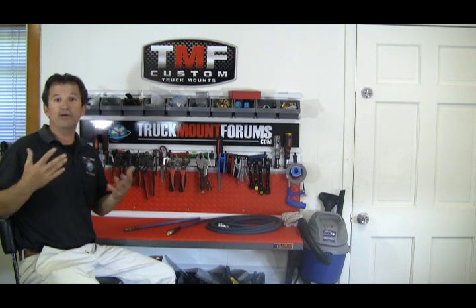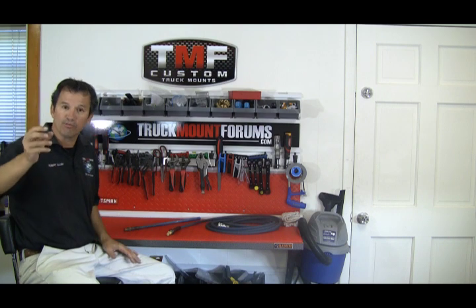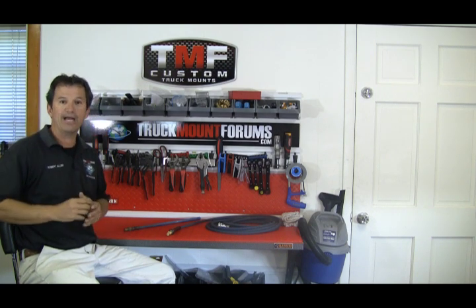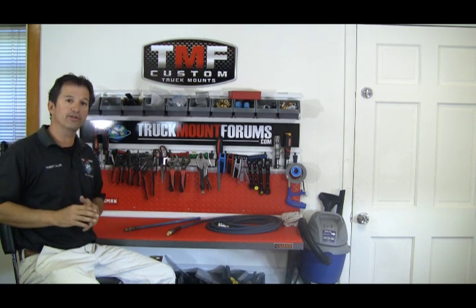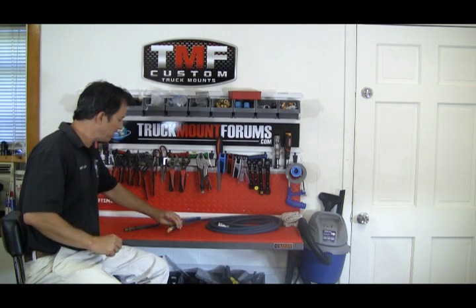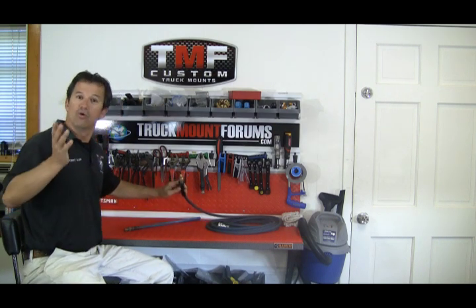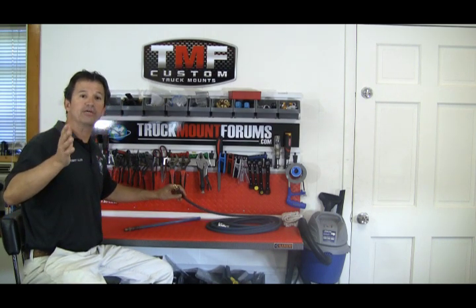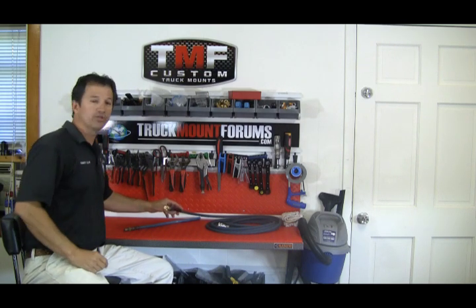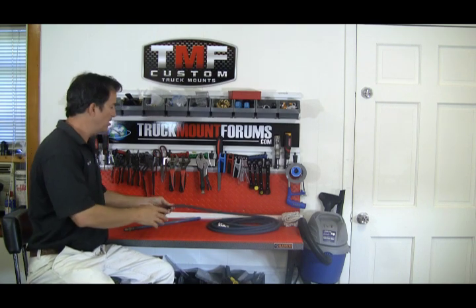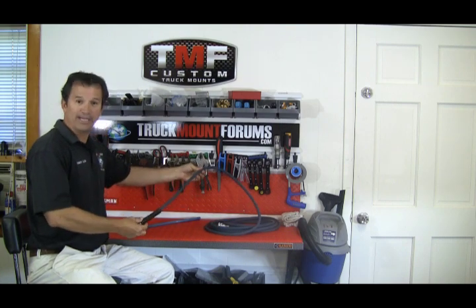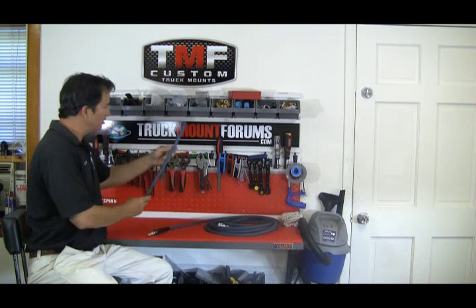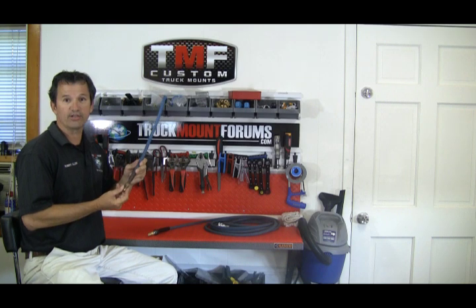That's why some major manufacturers put a bleeder valve on it so you can bleed it out. A quicker way, which is what we do, is use a solution line. One tip: we replace our solution lines about every 6 months regardless of whether they need it, especially with fuel burning technology, which leads to high heat and can cause hose failure. We take a hose, cut off about 18 to 20 inches, and leave the male quick disconnect on it.